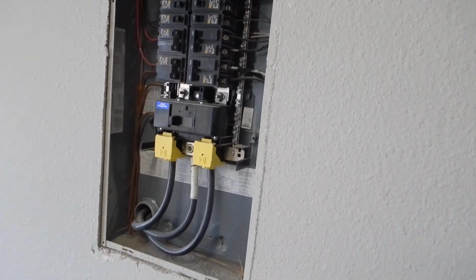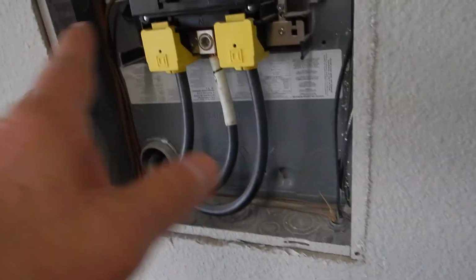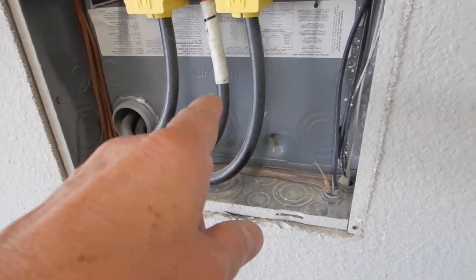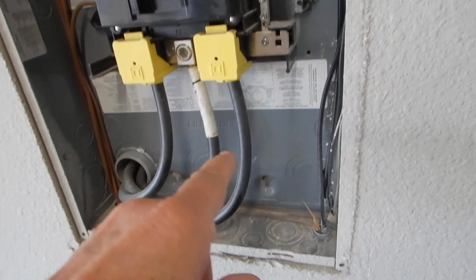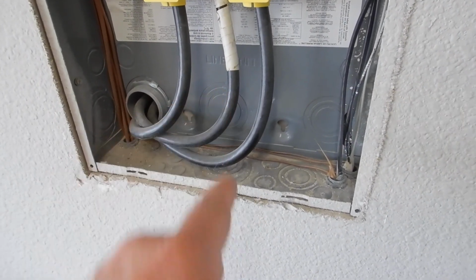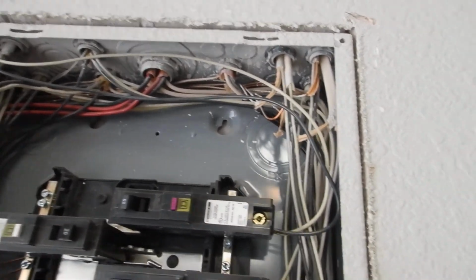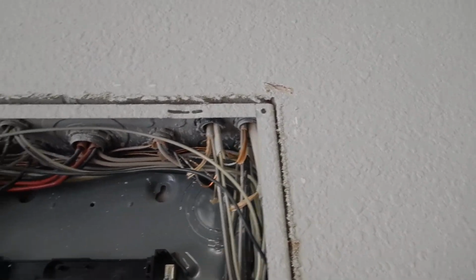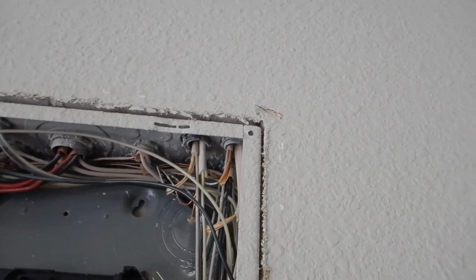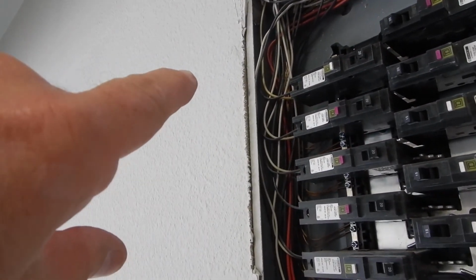This home is occupied. So what's going on here? Oh, not much. You got your protective covers, you got your white hots labeled black, you got your neutral labeled white, so you got everything separated right here. It's kind of unfortunate that there's some paint inside of the cabinet, right there at the top. But you're not supposed to have wires touching the cabinet cover.